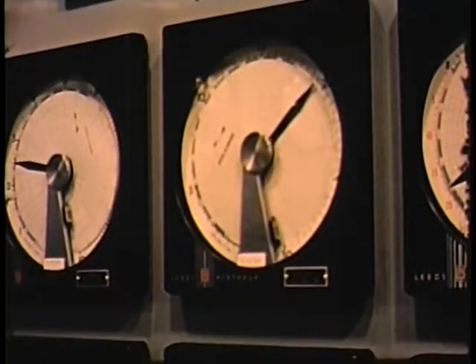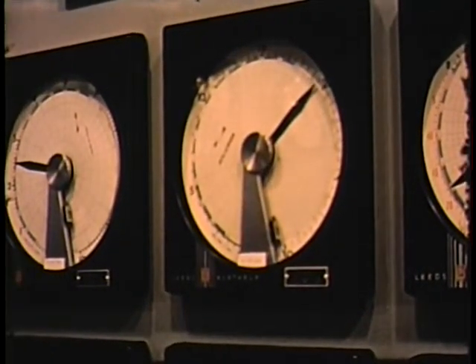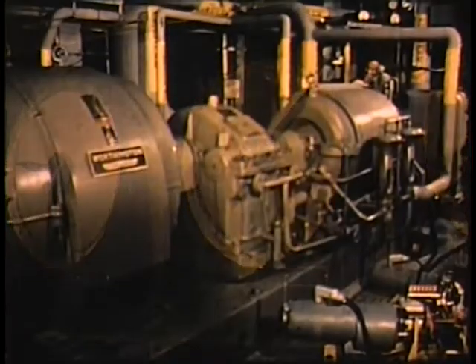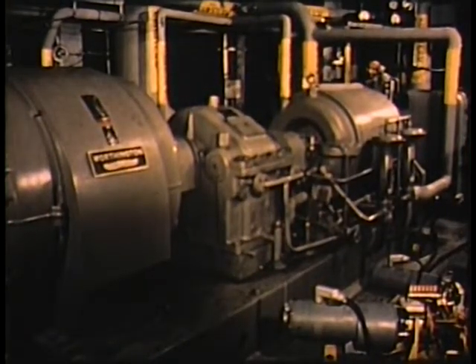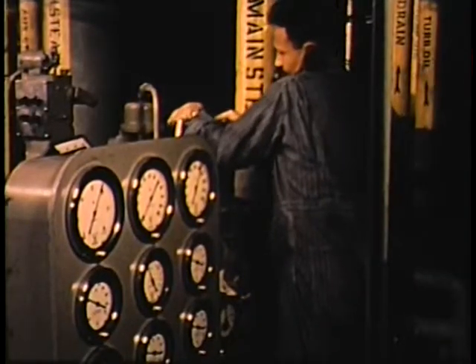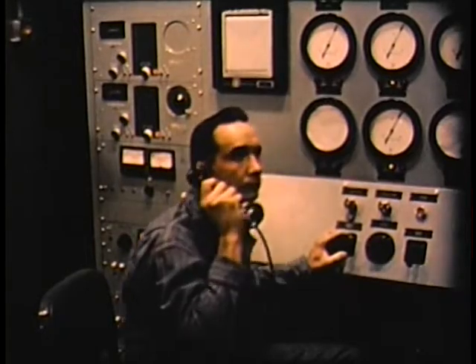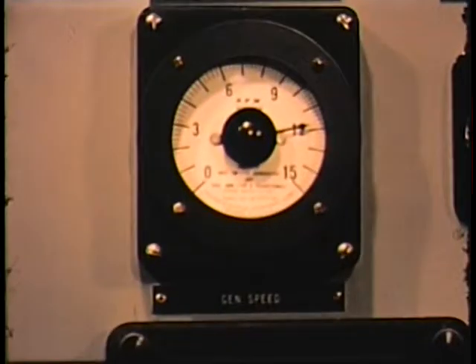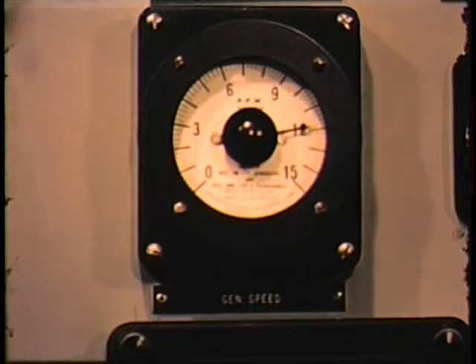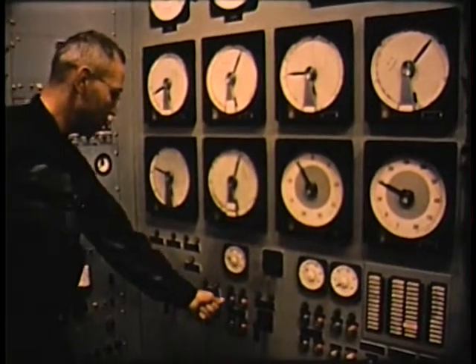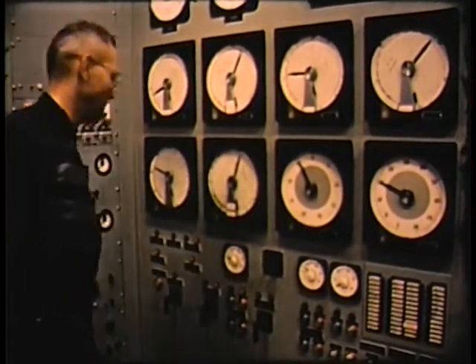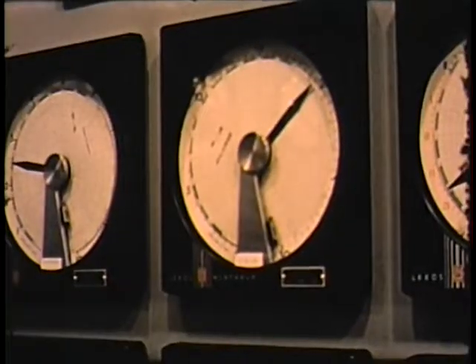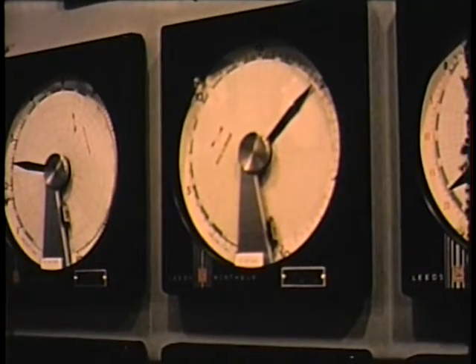The steam leaves the vessel through the main steam line. In normal reactor operation, the major portion of this steam is passed directly to the 300 kilowatt turbine generator set, providing enough electrical power to satisfy electrical load requirements and to operate the auxiliary equipment of the plant itself. The balance of the steam is passed to a heat exchanger to maintain hot water in a secondary space heating system. The mass flow rate of steam to this exchanger is controlled by a thermostatic element in the secondary circuit.